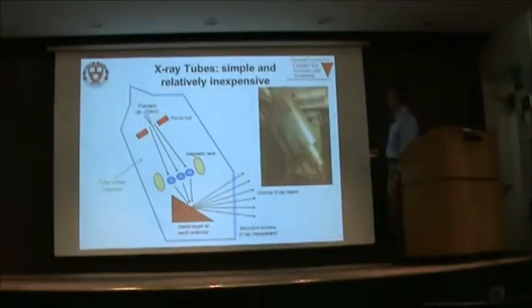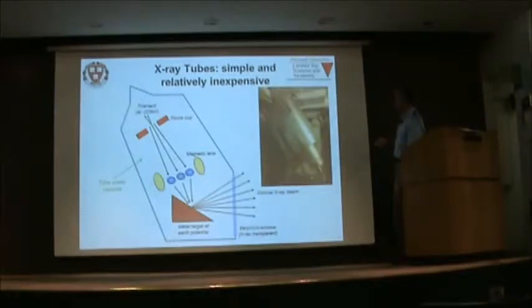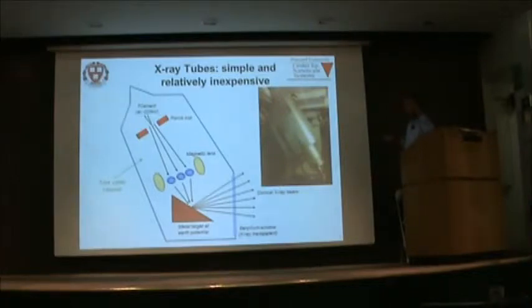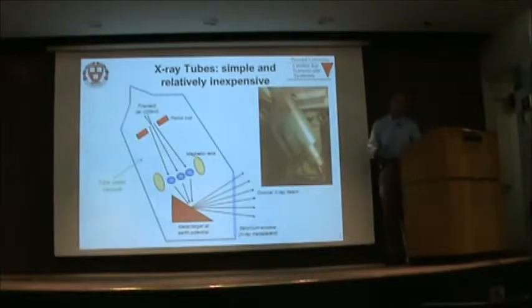This is a picture showing the X-ray tube in our system. The black part is the high voltage cable. The filament is behind there, and this part is the magnetic lens. Down here is where the metal target is located — it's cooled by water, so the blue lines are water lines. There is a small beryllium window where the X-rays come out.